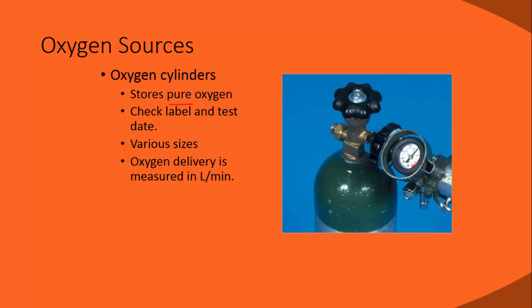So pure oxygen is delivered into these tanks. The tanks have to be tested, and the weak points of the tank are generally right here where this neck is, where the external connection for the valve exits - it's kind of threaded on the inside and screws in. But if this is fractured, then this becomes a projectile. Gas will escape this way, and this will move that way. Under high pressure, this could certainly kill somebody.